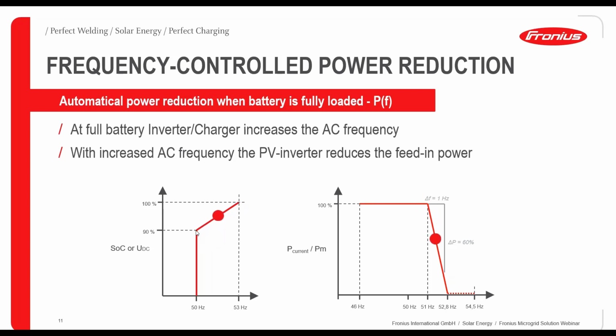Once the SOC value is reached, the frequency is increased, and the output power is reduced accordingly. Up to a specific frequency, the inverter is completely controlled and does not produce if necessary. That's the perfect communication between Fronius and Victron.